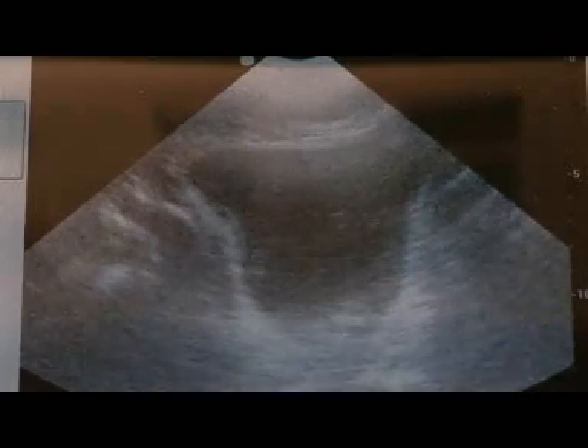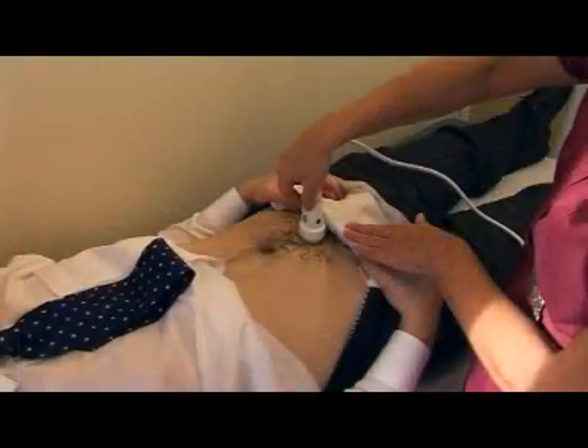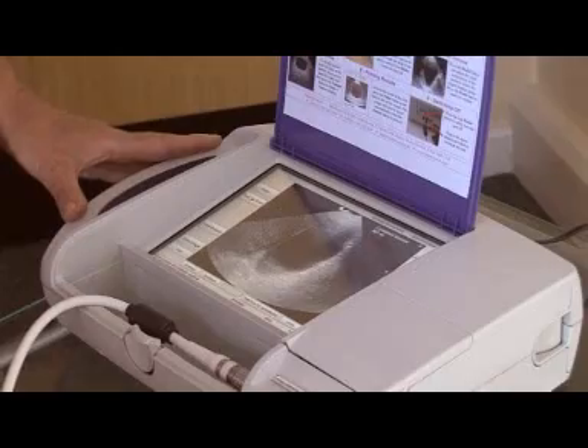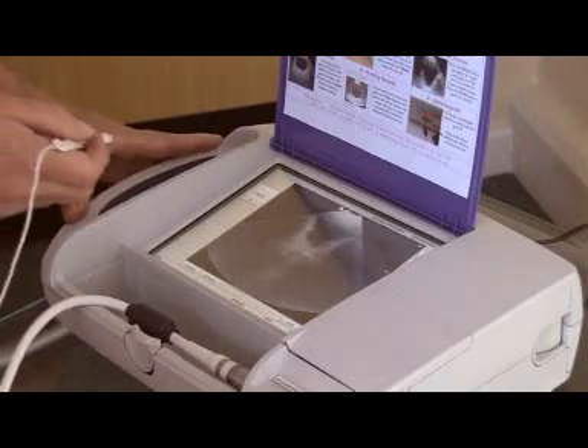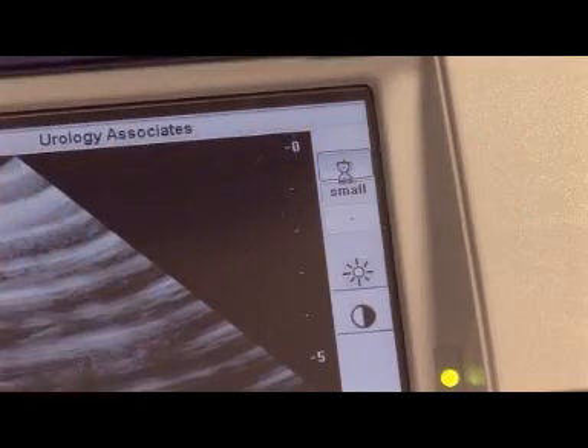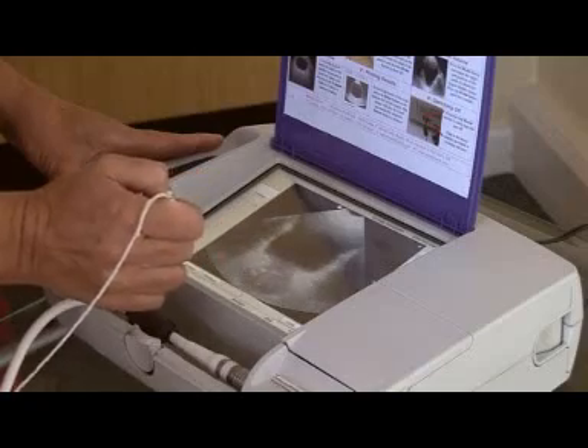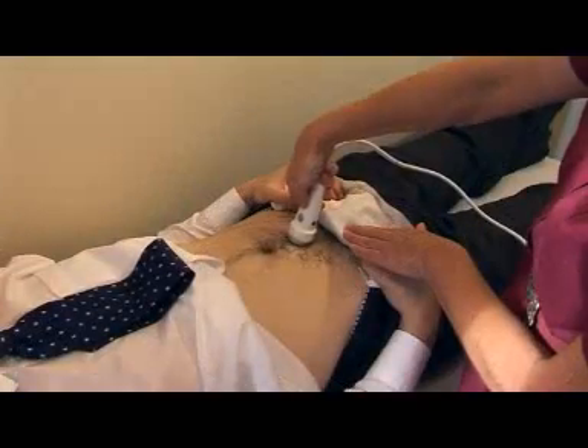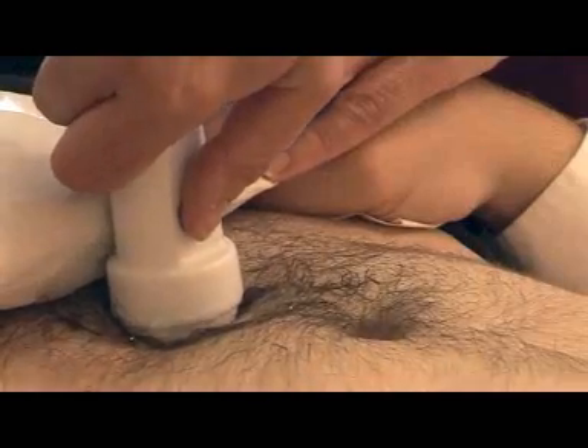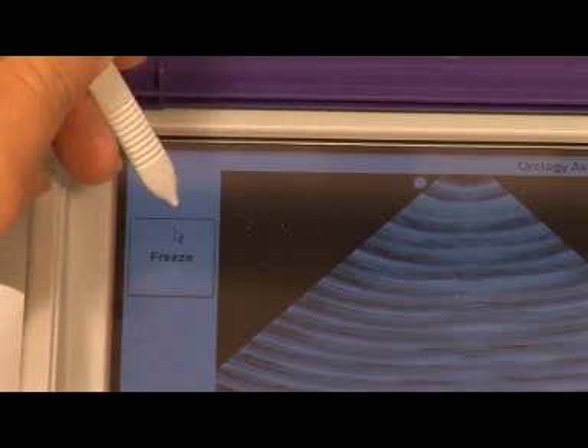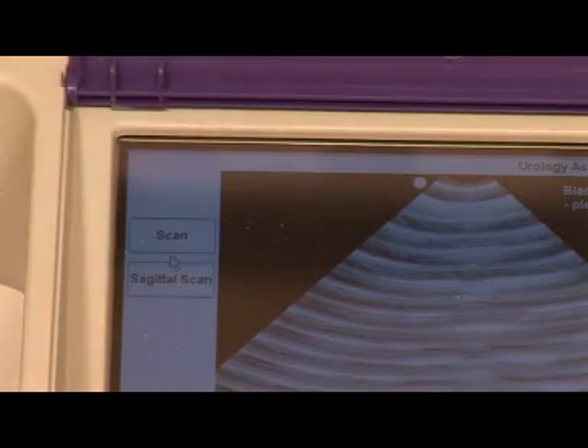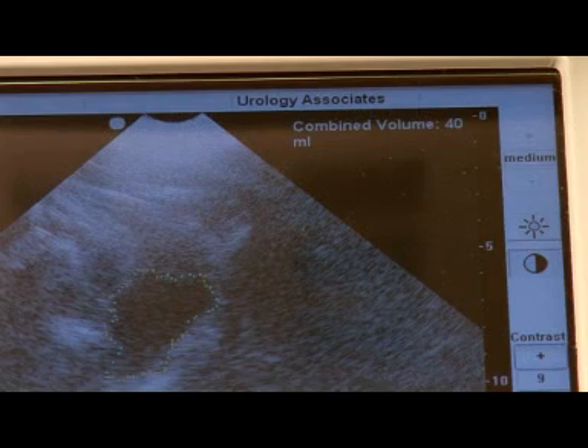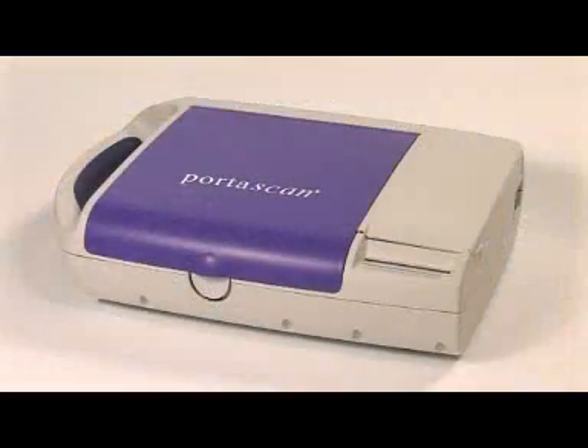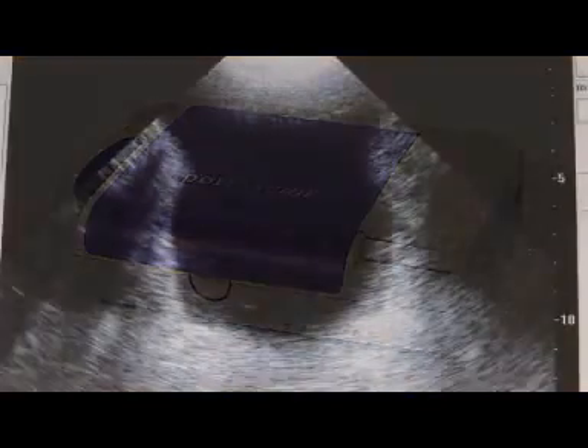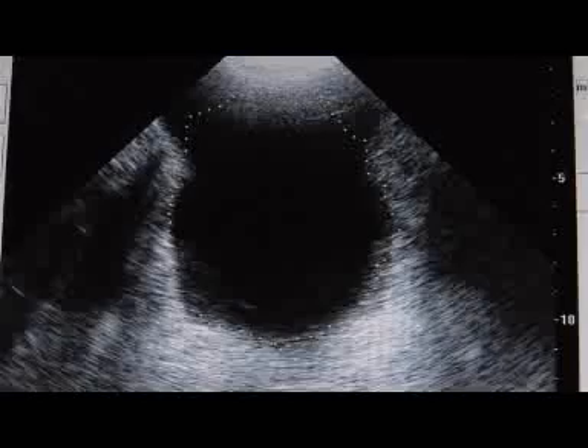The bladder is the dark area coming and going as the probe is moved. If the bladder is too small or too large for the screen, press the depth buttons to obtain the optimal scan image. When it is at its most prominent, hold the probe steady and press the blue probe button again or the freeze button on screen to freeze the image and calculate the volume. The Portascan Plus identifies the bladder by drawing a line around its outline.